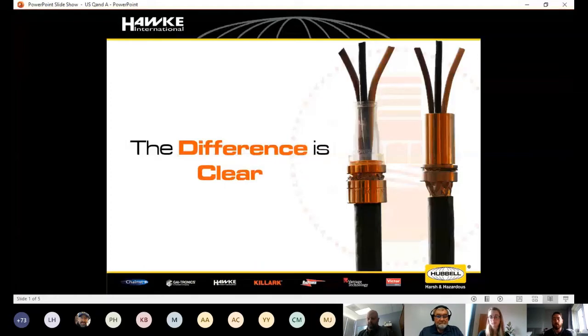Now you filled that with a putty, and you could remove that once it was hard, and you could see whether it was filled correctly. And it had filled all the voids, and the putty had moved around all of the cores. Now, obviously, with that design, and obviously the movement that we are definitely behind the curve on, which we're trying to catch up with now, is the introduction of a liquid pour seal. With a liquid pour seal, it acts slightly differently when it goes harder, and the adhesion between the actual epoxy resin that we use and the plastics that we use in these compound chambers wasn't possible in the old design. So we had to develop something new.